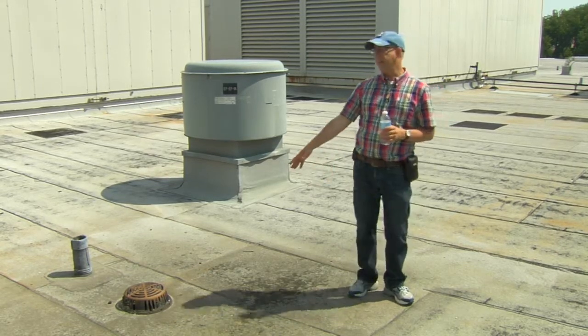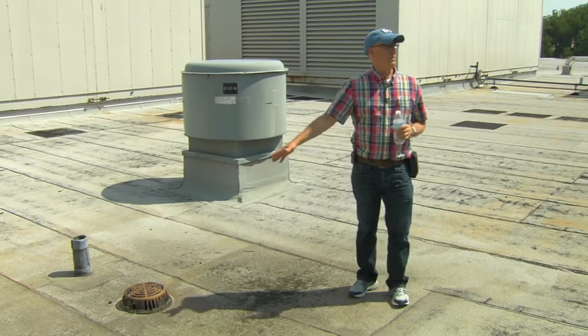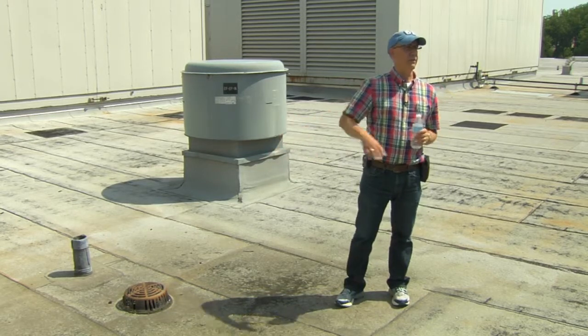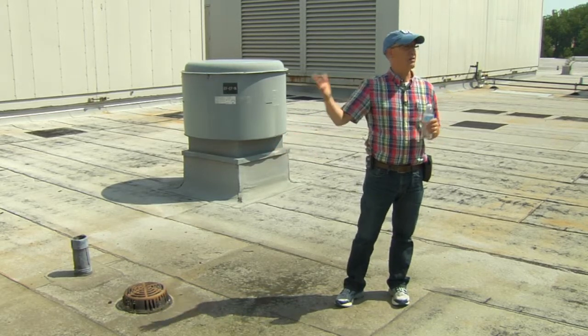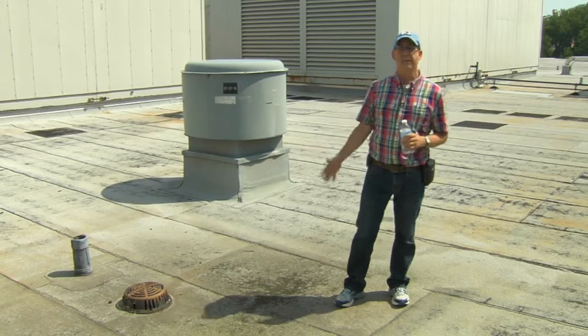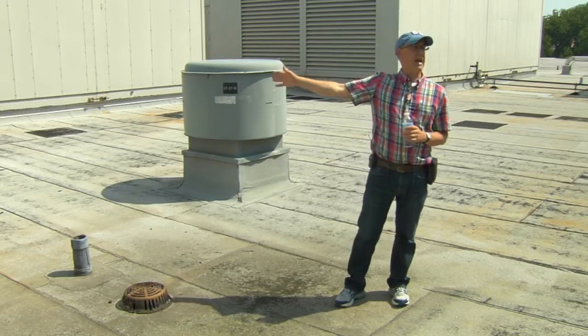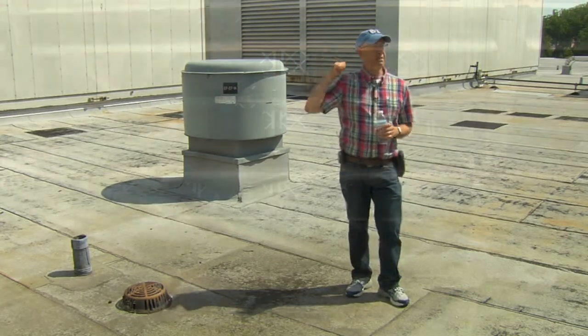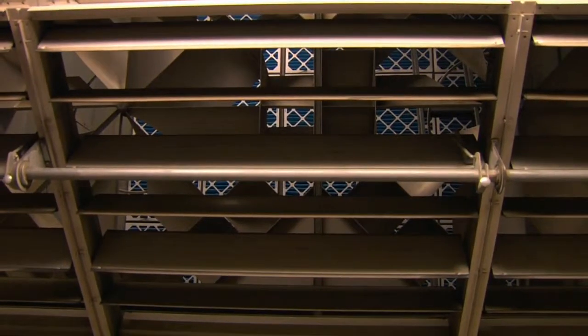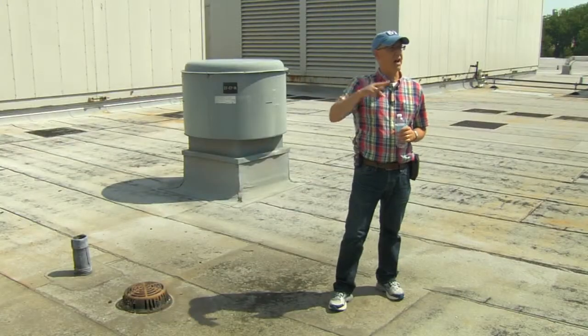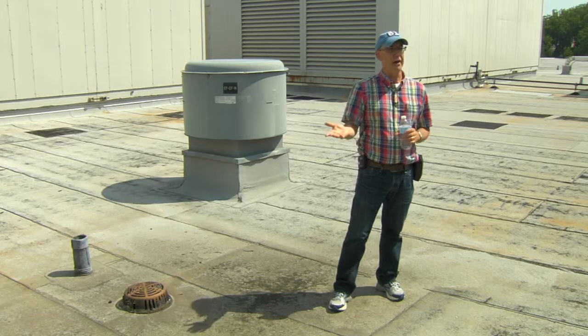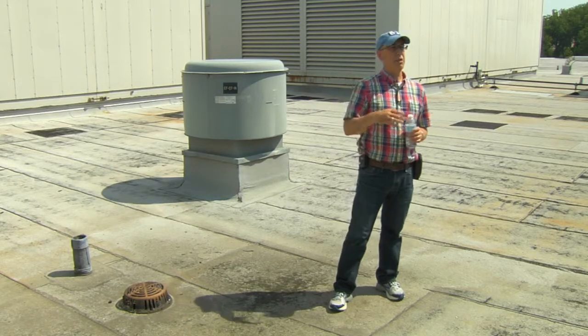If I've got snow melt, heat trace, are those active? Gutters, are those on right now this time of year? They hopefully are turned off. When we jump into the air handler boxes here, we want to spot check filters. We want to make sure if equipment has hand-off-auto switches that they're all in auto. So those are some of the things we want to look at.